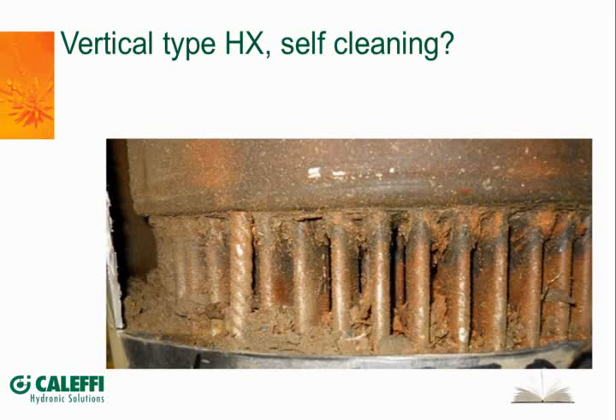This is low velocity, very low pressure drop on the water side, so there isn't a lot of force to flush this stuff through this type of boiler. It's nice because you can do total circulation through them, but that means you need a clean system to do it.